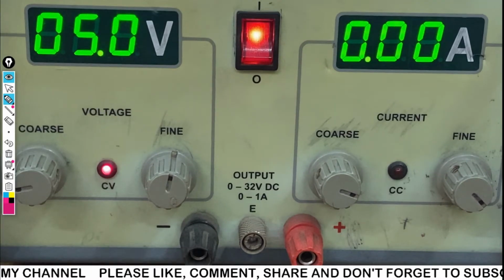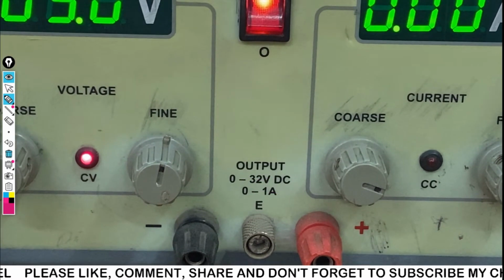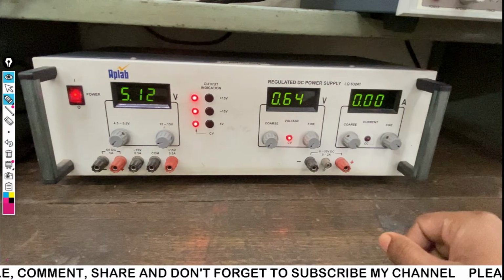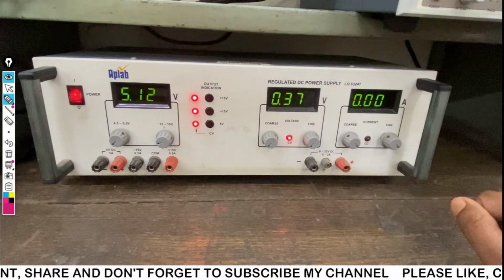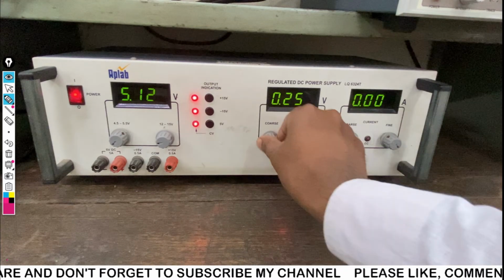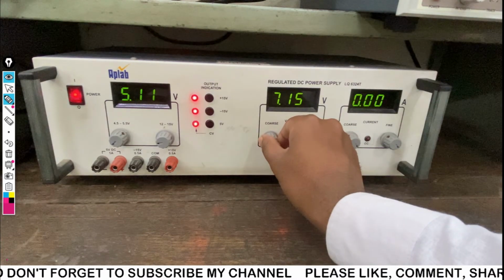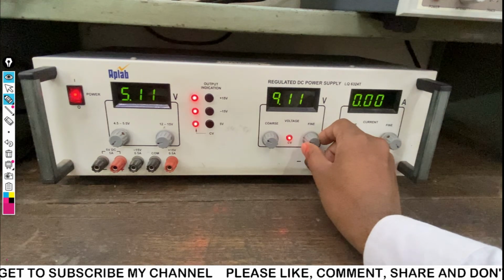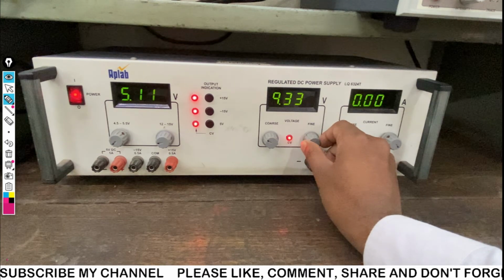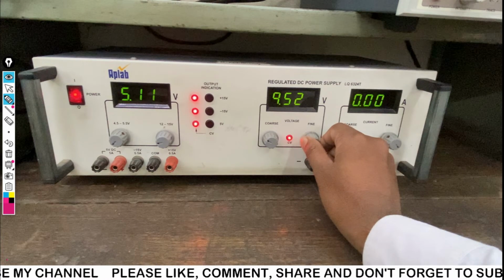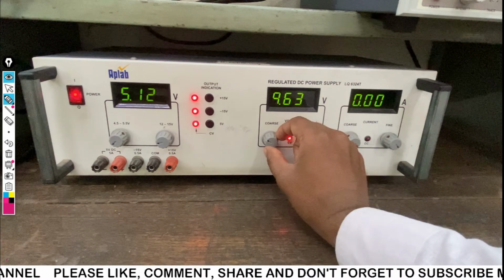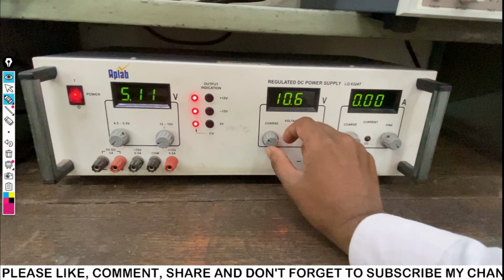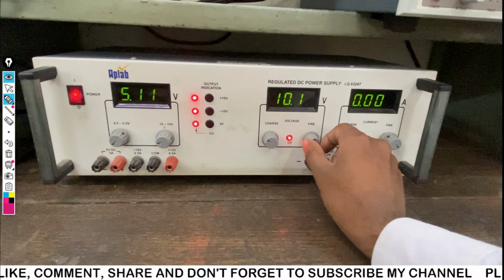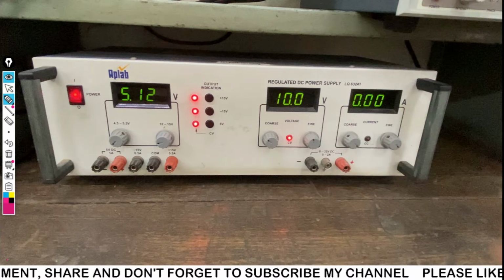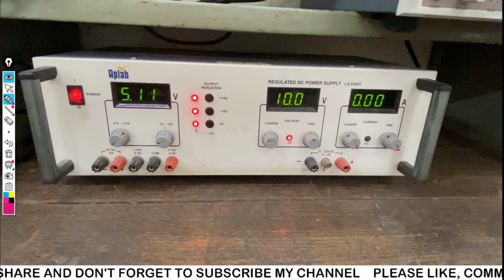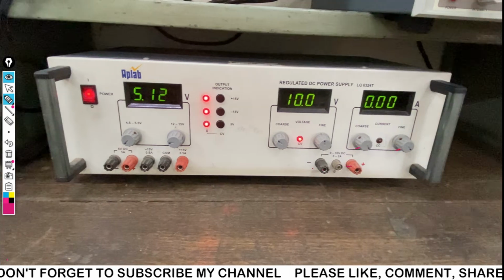You can see here this is a 32 volt and 1 ampere maximum rating of this power supply. Look at here, this is again one power supply that I explained in the front panel. This is a regulated DC power supply. We can adjust using the coarse and fine buttons over here. If I am going to adjust to 10 volt, look at here, I keep the fine adjustment at the middle, then do the coarse adjustment, and then a very minimal adjustment to set it at 10 volt. Keep in mind that at that time the current knob is at maximum, so this plus and minus will give us a 10 volt DC power supply.